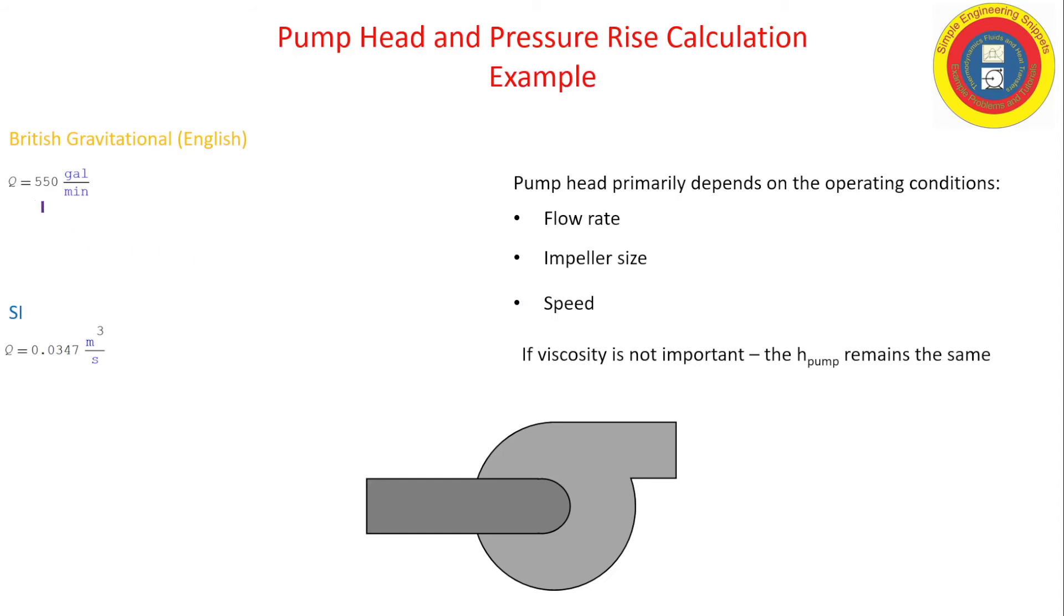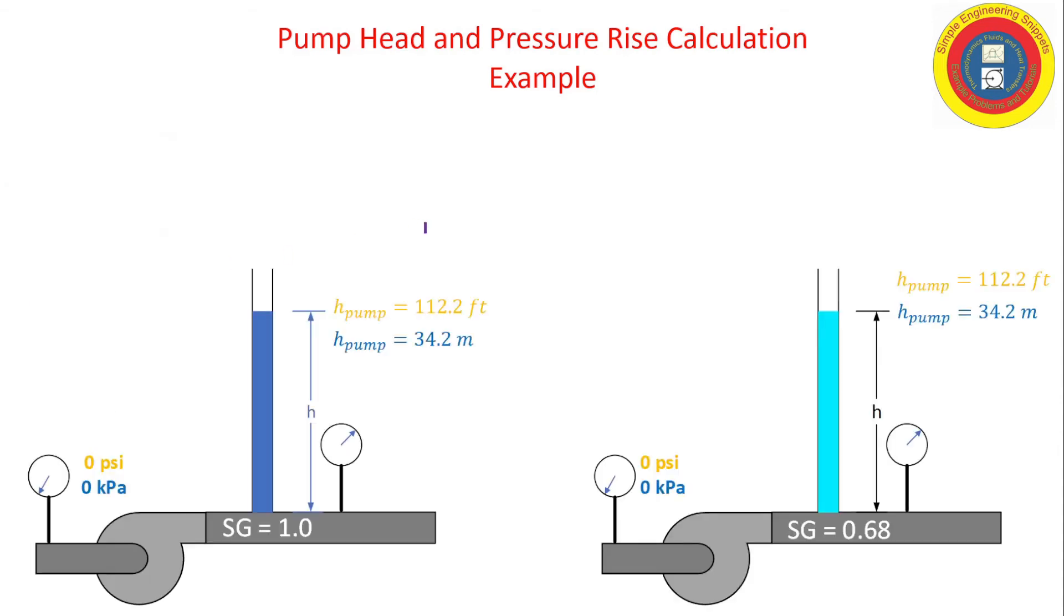Okay, so when that is true, then the pump head remains the same. So we have the same pump operating at the same speed, we're going to be analyzing for the same flow, and so the pump heads remain the same. Now this is sometimes not intuitive, so let's take a look at it graphically. On the left side, we have specific gravity equal to one, we have the pump heads, and we don't know what the pressure is—we're going to calculate that. And for specific gravity equal to 0.68, the gasoline, again the pump head is going to be the same.